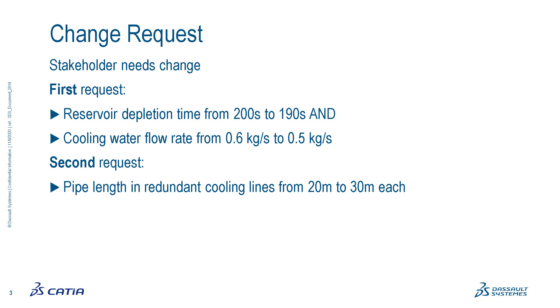So what are the changes? We'll have two requests. The first request: water reservoir depletion time shall change — the expected depletion time from 200 seconds to 190 seconds. So what should be the size in order to deplete the reservoir without refill in the given time? And cooling water flow rate will change from 0.6 to 0.5 kilogram per second. The second request: pipe length in redundant cooling lines will change from 20 meters to 30 meters each.